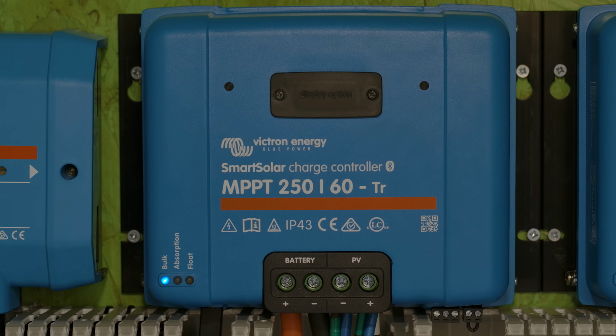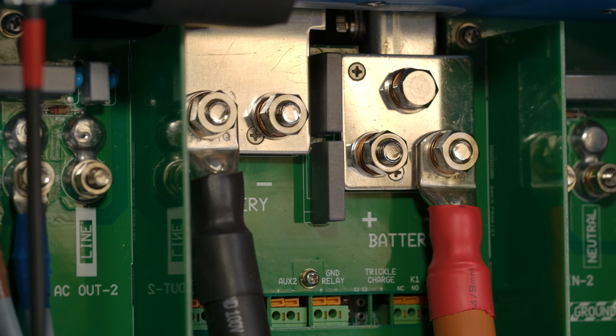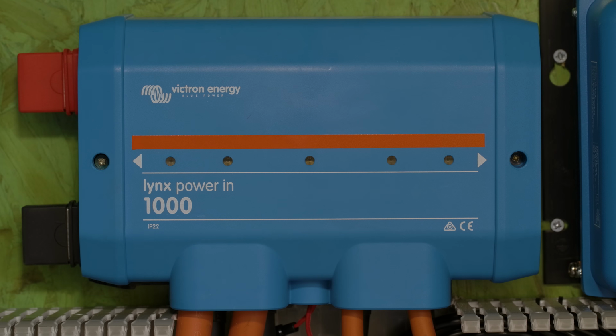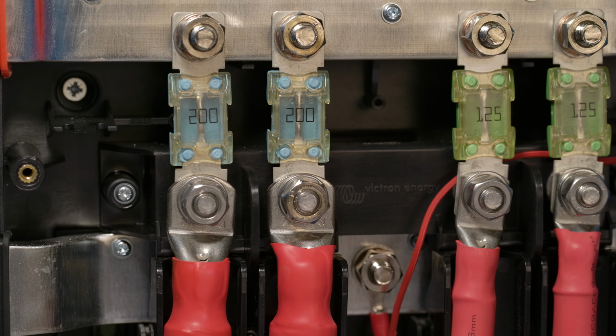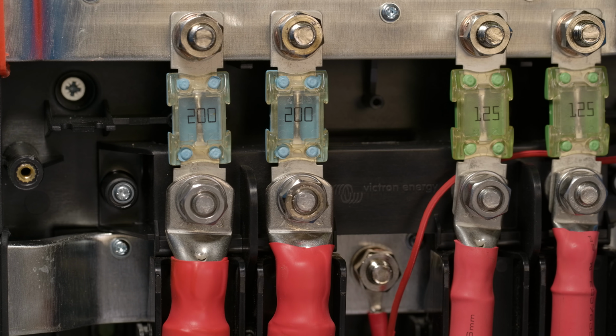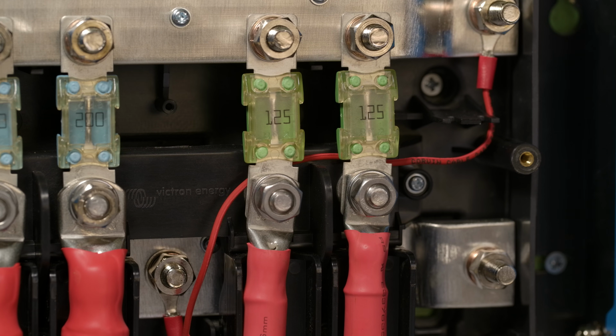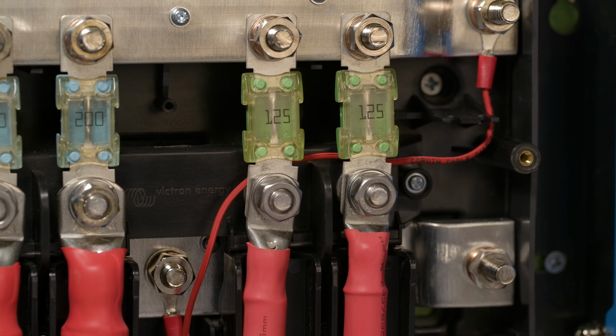Correctly sized cabling from each of the charge controllers and the Quattro inverter charger are wired through to the bus bars within a Lynx power in. A 200 amp mega fuse protects the Quattro, and each MPPT is protected by 125 amp mega fuses.